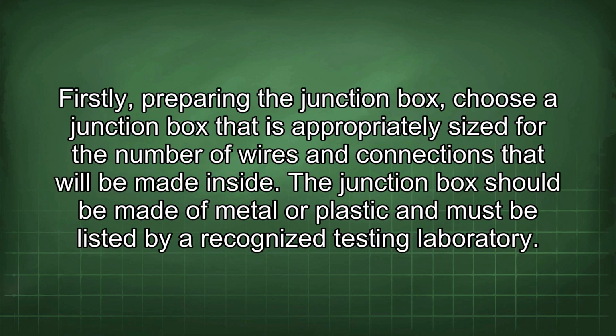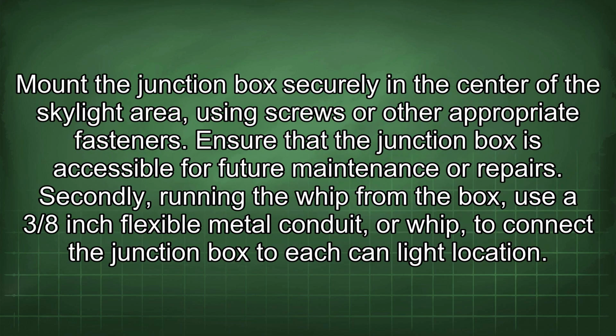Firstly, preparing the junction box. Choose a junction box that is appropriately sized for the number of wires and connections that will be made inside. The junction box should be made of metal or plastic and must be listed by a recognized testing laboratory. Mount the junction box securely in the center of the skylight area using screws or other appropriate fasteners. Ensure that the junction box is accessible for future maintenance or repairs.